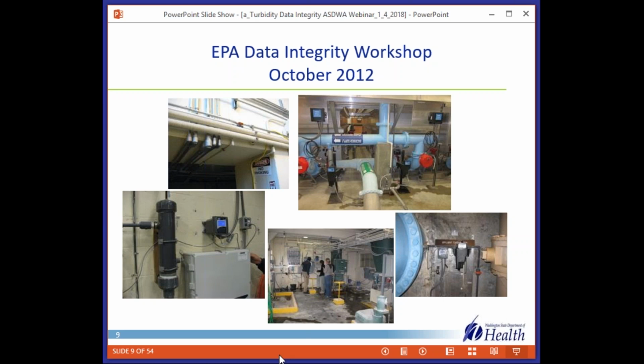The genesis of this turbidity data integrity project was an EPA data integrity workshop in October of 2012. It was held at a local water treatment plant, and it consisted of 3 teams spending the entire day looking at nothing but turbidity, from the sample tap through the instruments to the SCADA system, and finally to the report that gets submitted to us each month. This was a real eye-opener for me. I had no idea how many factors there were that could influence the data that we received.